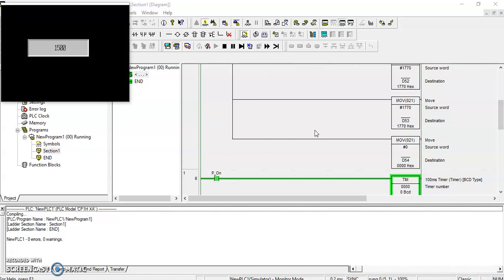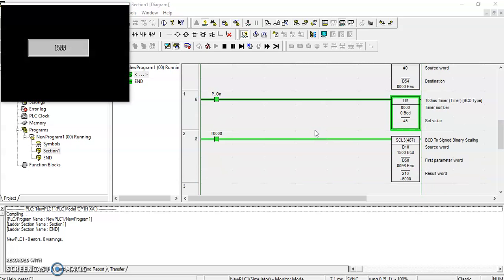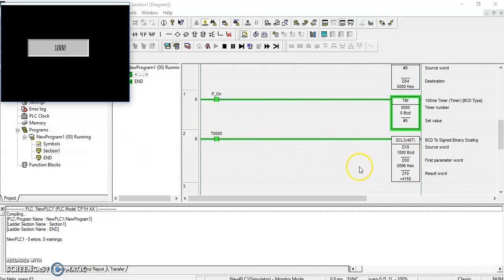So running the system, we could observe here that as we put a certain amount of voltage, our desired output voltage, it would tell the system this is the amount of voltage that we need. So at 1500 volt, if our needed voltage is 1500, it's going to tell the system it should give out the max amount. So let's say we just want 1000, enter. This would be the 1000 value for the system.